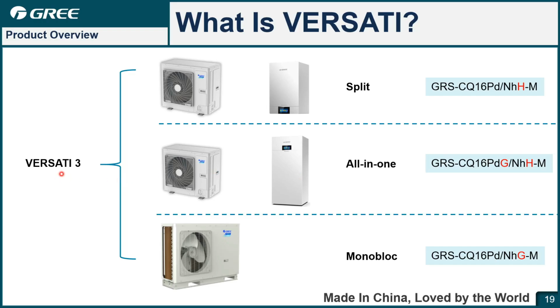So for the VERSATI 3, there are 3 types. The first one is a split. Outdoor unit, hydro box, and water tank are separated. And you can see here is the nomenclature. If there is H, that means the split type for the VERSATI 3. Another one is the all-in-one, also an outdoor unit. However, the hydro box and the water tank are integrated. They are together, just one casing. And you can see in the nomenclature, here G stands for all-in-one. That's the difference from the regular split.